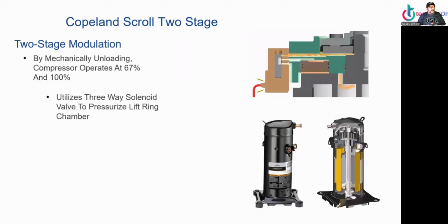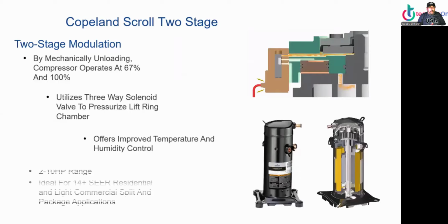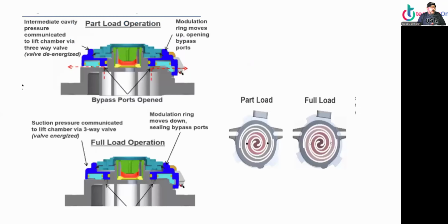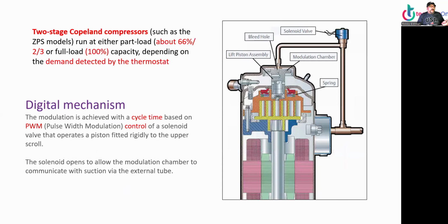It utilizes a three-way solenoid valve to pressurize the lift chamber. It offers improved temperature and humidity control. A 2 to 10 horsepower unit, ideal for 14 SEER residential and light commercial split air conditioners. SEER stands for seasonal energy efficiency rating. Now, part load. I'm not going to go into details with it.